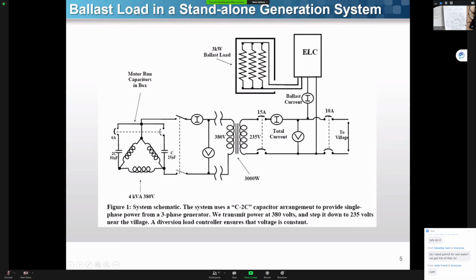But at the same time, here's the electrical load controller to match. They have those ballast loads or dump loads. So if the village, maybe your house or wherever, requires more power down here, they will bring less power to the ballast. But if you require less power down here, they will bring more power to those ballast loads.